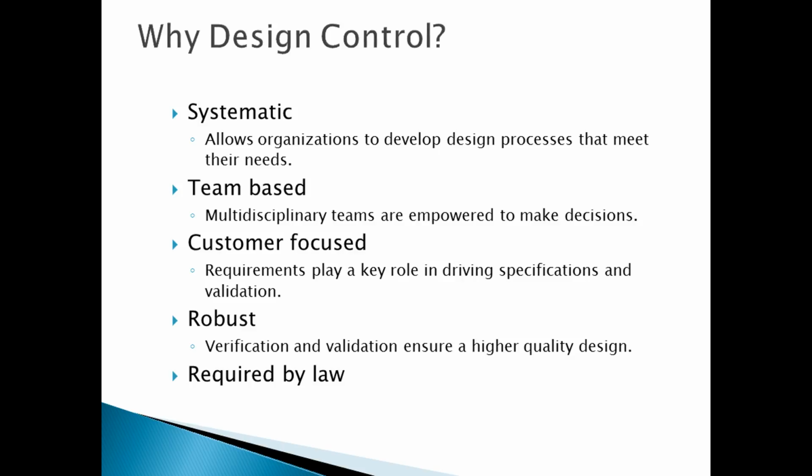It's a very robust process because of these two feedback loops that are involved, and those feedback loops are verification and validation, ensuring that what you're producing was what the customer required, or the patient or the doctor required, in the first place. And then finally, it's required by law. It's federal law that all medical devices be designed using these standards. So, you know, it really raises an interesting question about what is a medical device.